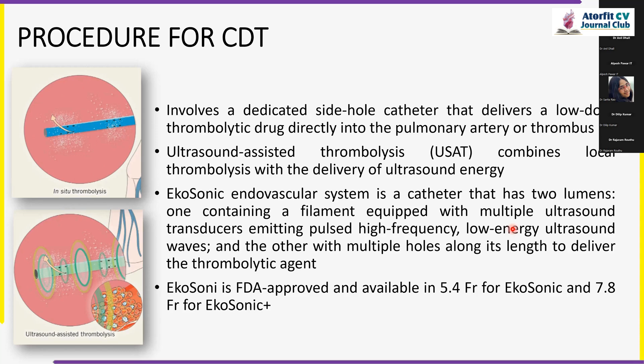So the ultrasound assisted thrombolysis can combine both the actions, which is you are not only giving thrombolysis, but you are also using ultrasound energy to break down the thrombus. EkoSonic endovascular system is the catheter, which has two lumens, one which contains a filament equipped with multiple ultrasound transducers emitting high frequency, low energy ultrasound waves, which help in breaking down the clot, and the other with multiple holes along the length to deliver the thrombolytic agent. So by using this catheter, we can use the two methods to deal with the thrombus. EkoSonic is FDA approved and it is available in 5.4 French for EkoSonic and 7.8 French for EkoSonic Plus. And these are currently available.